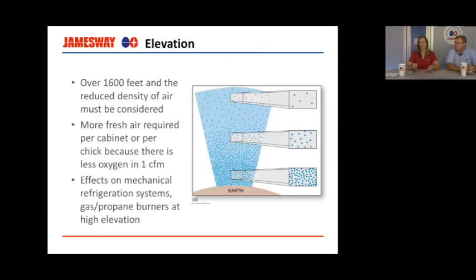So elevation. If a hatchery is located over 1,600 feet above sea level, the reduced density of air must be considered. So we actually require more fresh air per cabinet because there's less oxygen in 1 cubic foot of air than there would be at sea level. And in some cases, if you're located at very high elevations, your mechanical refrigeration systems, so your rooftops, your chillers, actually need to be designed with different components in them, also maybe your gas or propane burners, to again compensate for the fact that there will be less molecules in a given volume.